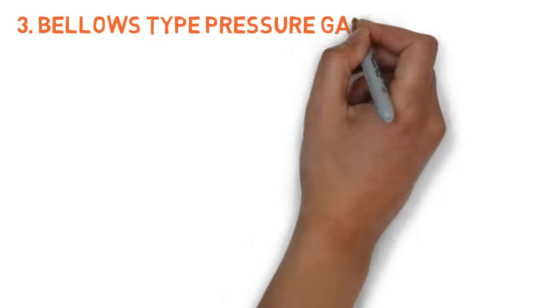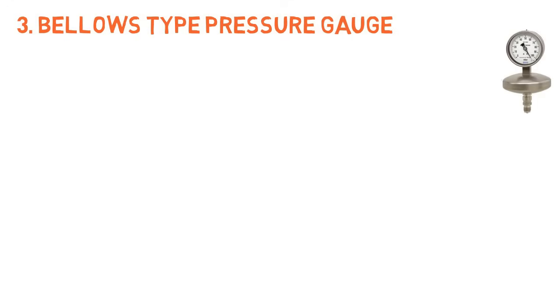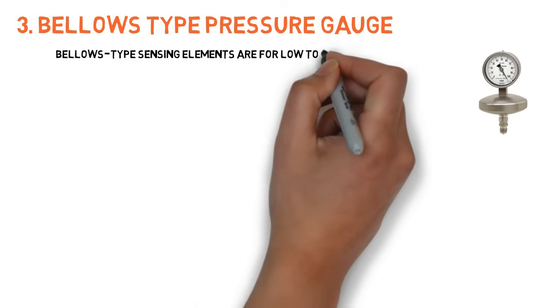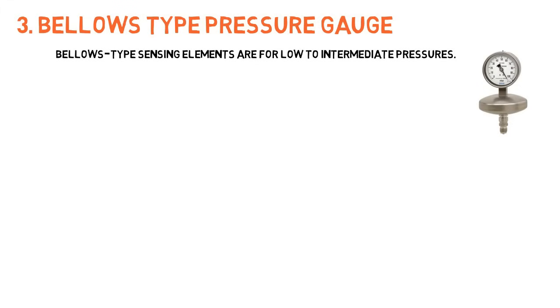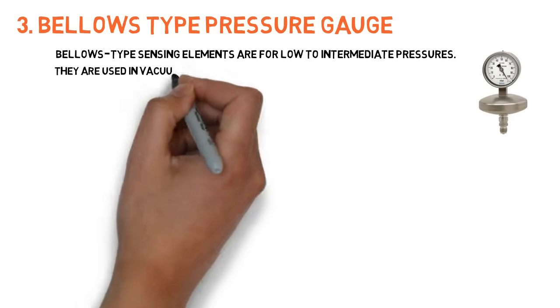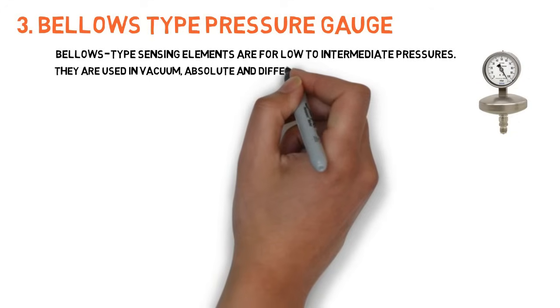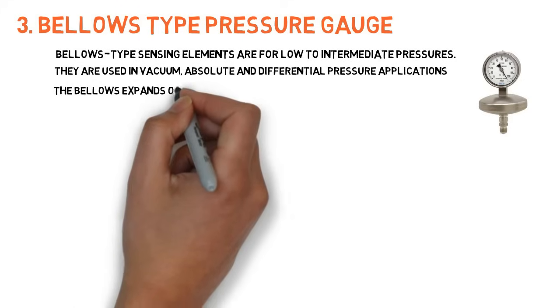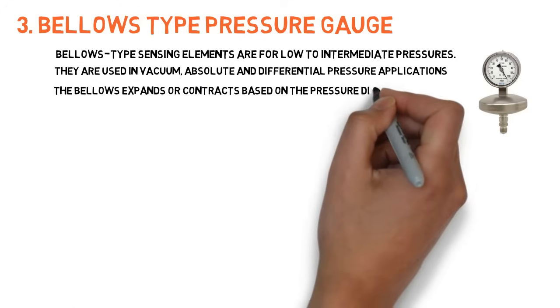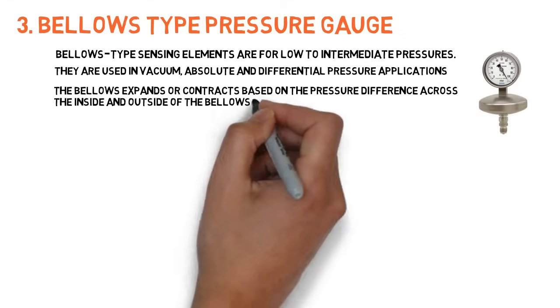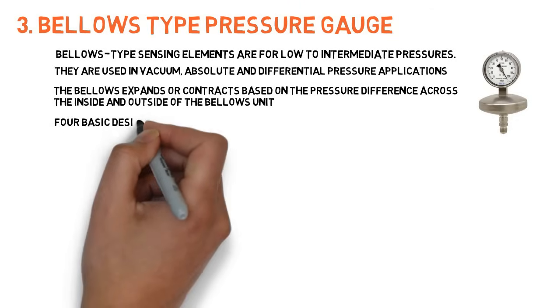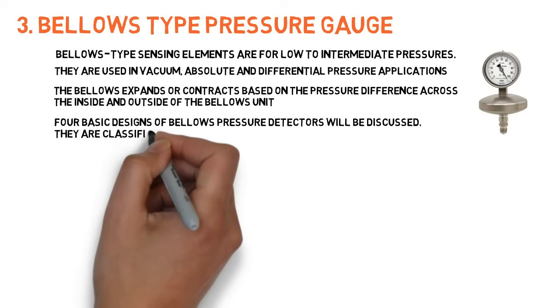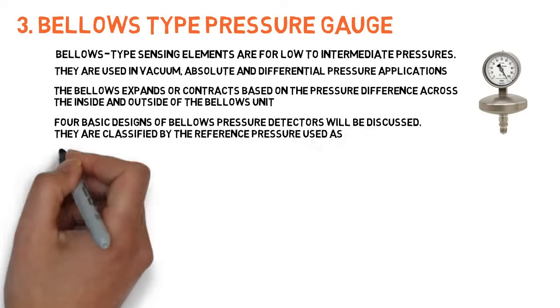Bellows type pressure gauge. Bellows type sensing elements are for low to intermediate pressures. They are used in vacuum, absolute, and differential pressure measurement applications. The bellows expands or contracts based on the pressure difference across the inside and outside of the bellows unit. Four basic designs of bellows pressure detectors are classified by the reference pressure used, as absolute, gauge, or differential pressure detectors.